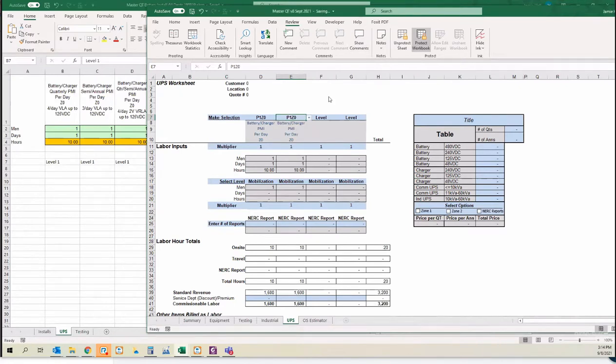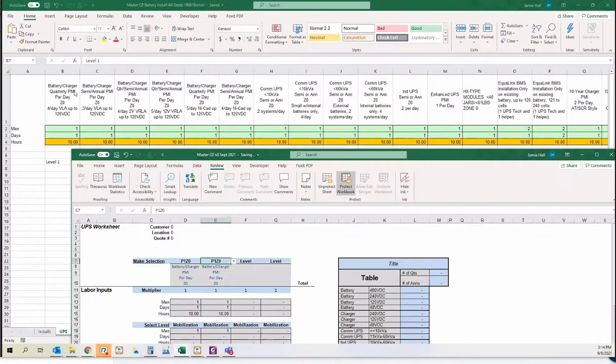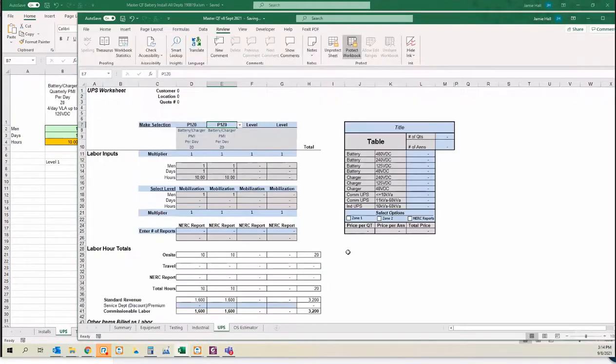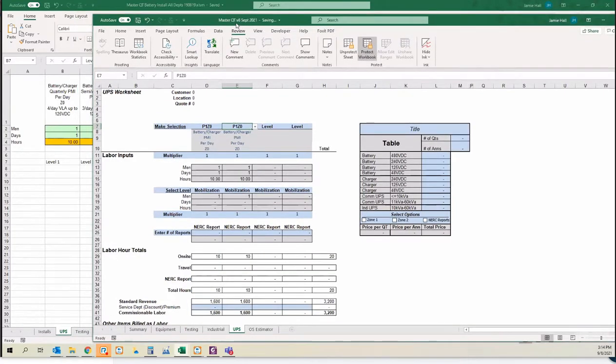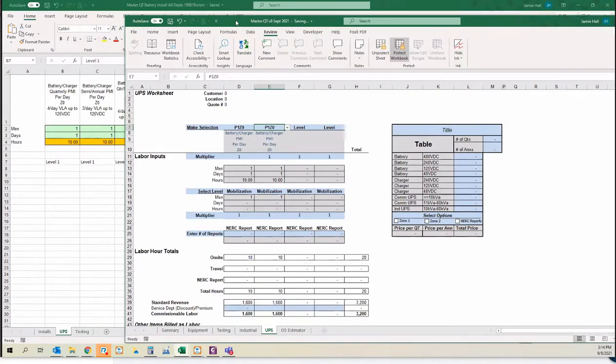Going off what this first one tells me, if I have a battery or a charger and I'm doing a quarterly PM, I can do 4 of them a day as long as they're 120 or less. So if an RFQ comes in requesting quarterlies, and they give me 4 different chargers and 4 different batteries, the unit name of the batteries should match the unit name of the charger on the site survey, which I haven't gone over with you guys yet, but once we get there it should be clear which battery goes with which. So you have a battery/charger system, and you're doing a quarterly PM — you can do 4 of them a day at 10 hours with one guy.